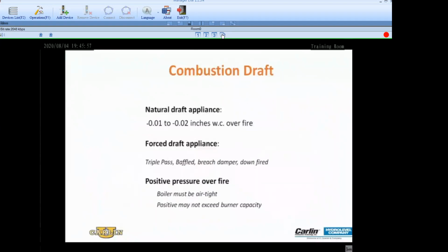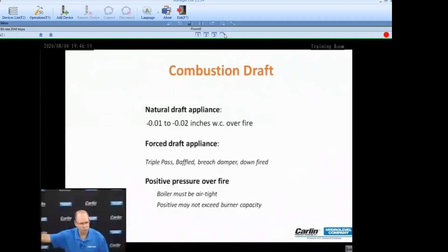Measuring draft. What are we measuring? What are we looking for? Well, every appliance manufacturer will tell you what they expect to see in draft over the fire. And in order to achieve the draft over the fire, this is what I need to see on the breech, on the smoke hood side of the appliance. So whatever draft I get back here determines the draft that I'm going to see here. If you're not measuring draft over the fire, you're wasting your time measuring draft at the breech, because that's telling you that your chimney is working, but it's not telling you what's happening in your combustion chamber.